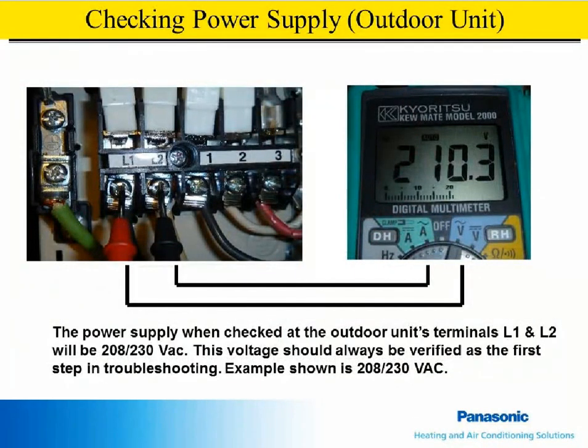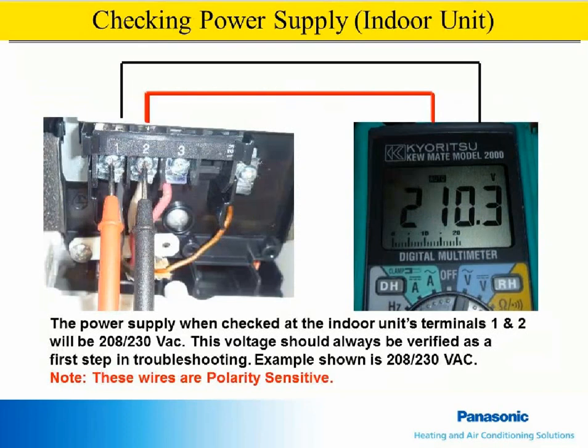L1 and L2 at the outdoor unit is power from the disconnect box. Terminals 1 and 2 at the outdoor unit is your power supply to the indoor unit and must be landed at terminals 1 and 2 of the indoor unit. Terminal 1 and 2 at the indoor unit should read the same voltage as terminal 1 and 2 at the outdoor unit. Remember, these wires are polarity sensitive and can't be crossed.